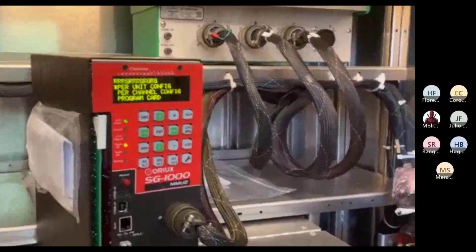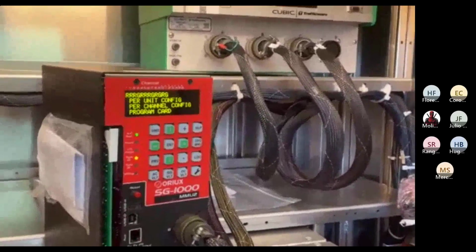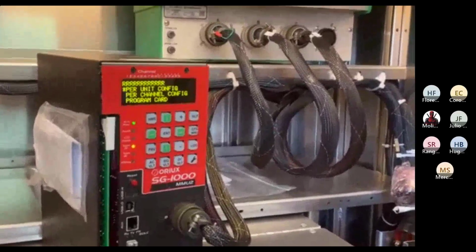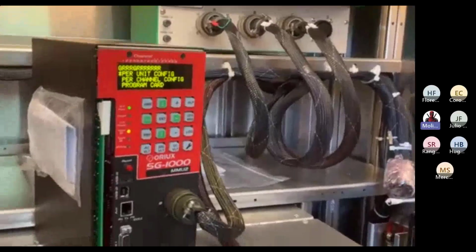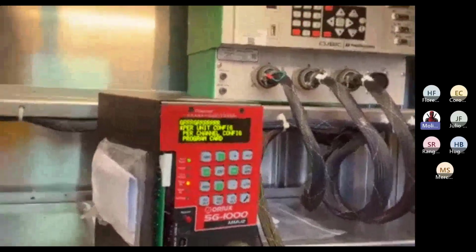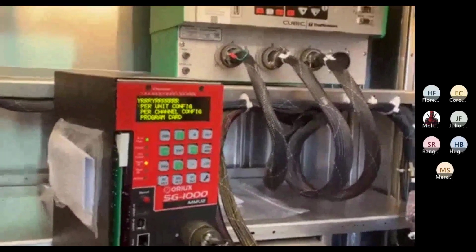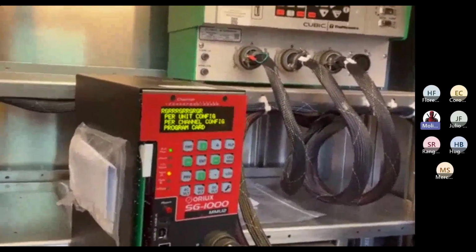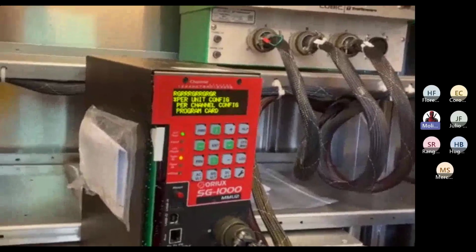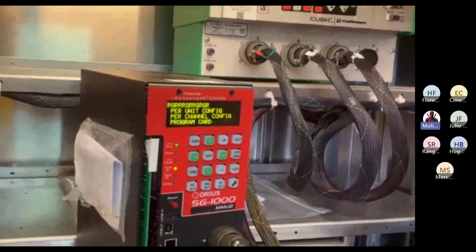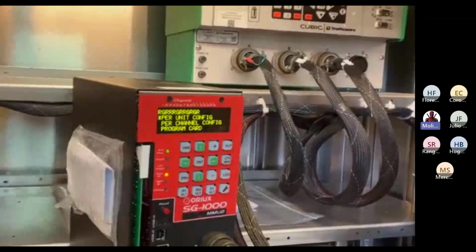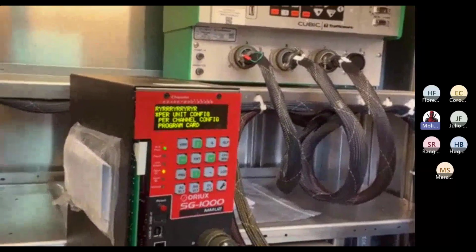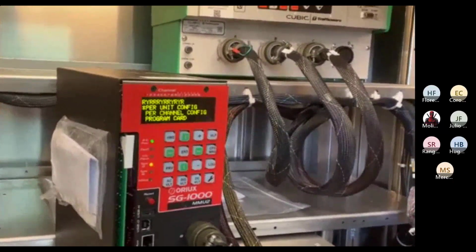See, in mine, I actually have the old TS1 12 channel jumper card. Mm-hmm. So we have different versions, right? If you had the full TS1 version, there'd be a little metal panel in the bottom of that, so you could only insert the 12 channel card in there, like the smaller one, and it would run only as a TS1. But you have the 16 channel cards. So if you go to hit config menu, and then hit enter on per unit config, and then hit the down arrow a couple of times so it says MMU type.